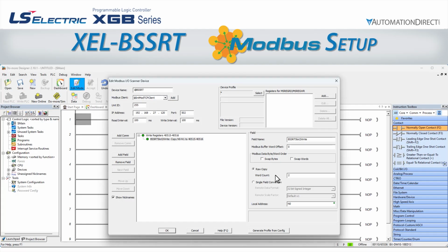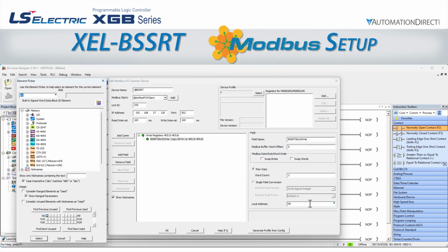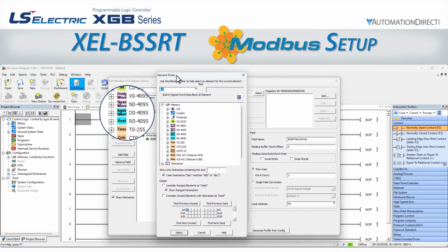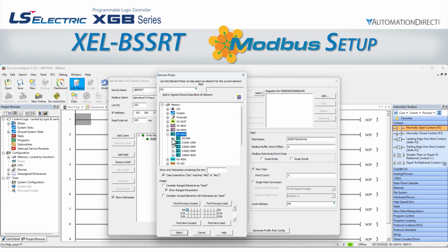If we were reading information from, or writing information to one of the more complicated modules, such as an analog module for instance, we might want to do a single field conversion for a specific data format, such as signed 16-bit integer. Our local address defaults to N0, which is a signed 16-bit register. We are handling 32 bits of raw information, so we would do better to use a 32-bit register. If we double-click in the local address field, it will open the element picker, and we can see that 32-bit signed registers will be D addresses. We can maximize the various levels until we can select D100.